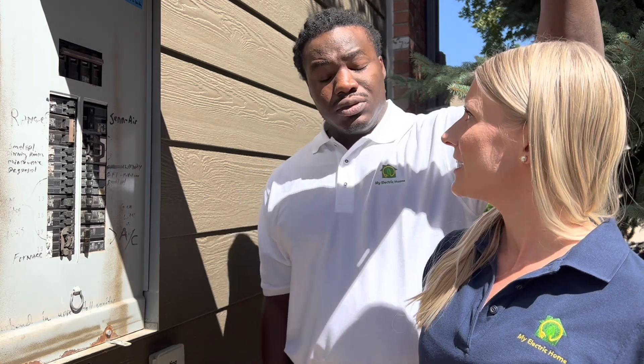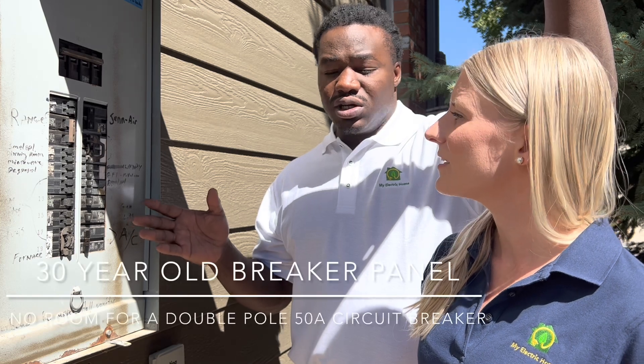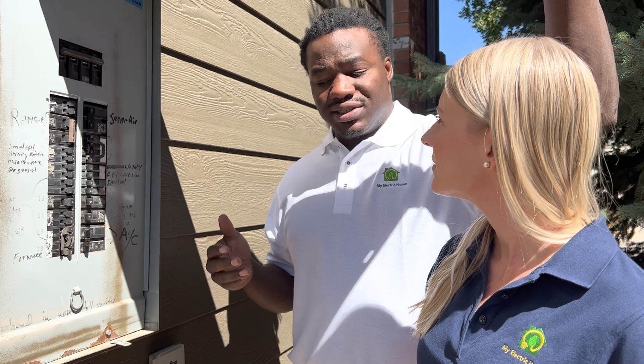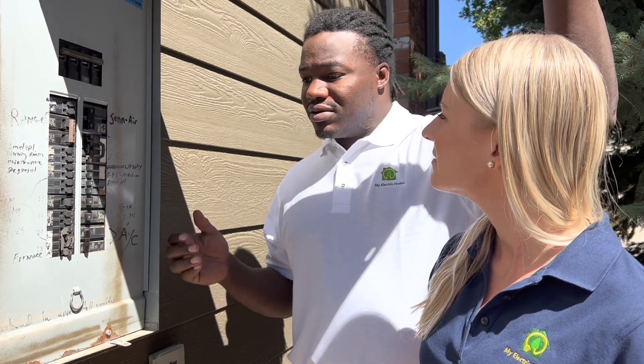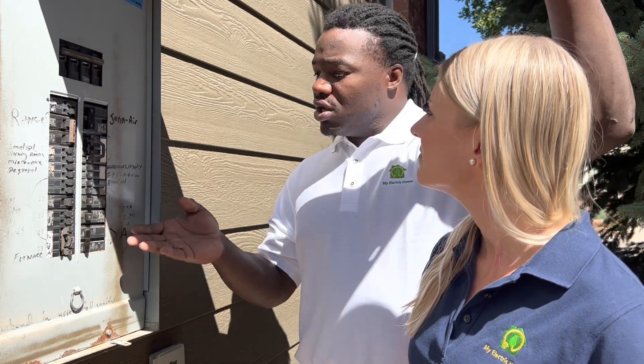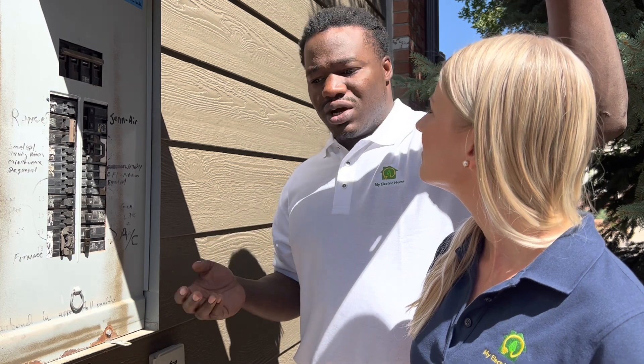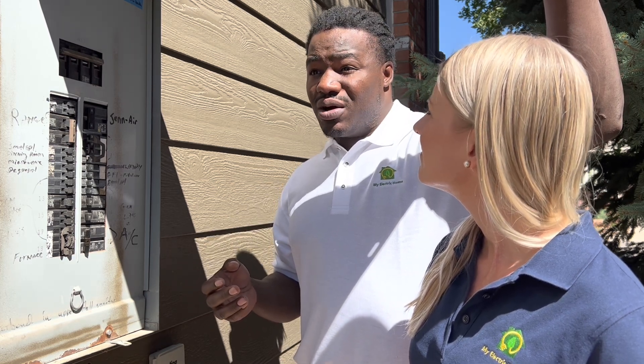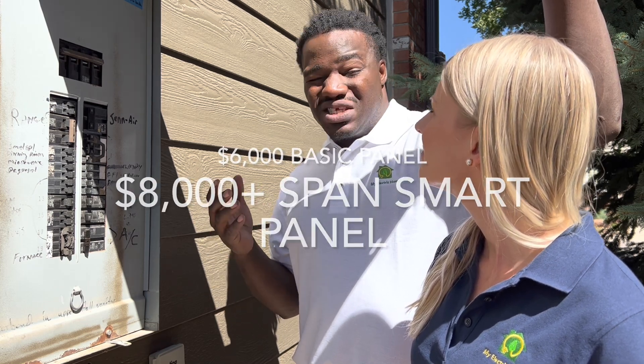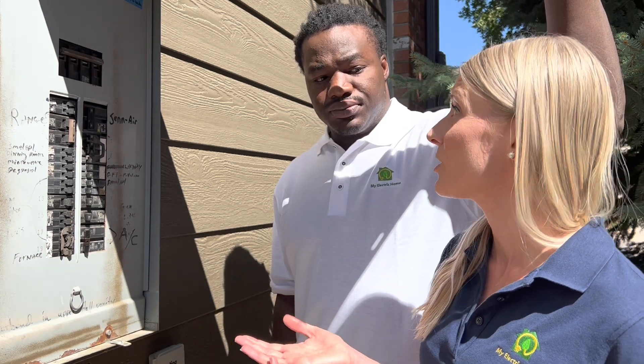So Jason, what are your thoughts on this panel? Well, unfortunately this panel doesn't have any breaker room whatsoever. So what we're going to have to do is a panel swap. Depending on what the customer wants — for example, a smart panel — that can increase the cost even more, though it comes with some pretty cool features. Factoring in permitting and materials, the total cost is probably going to be upwards of six grand, maybe up to ten thousand at the top. So if you have an older panel with no open spots, you should expect a bigger bill.